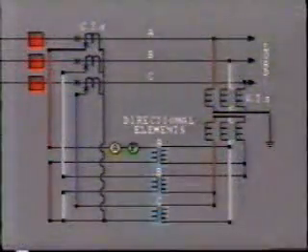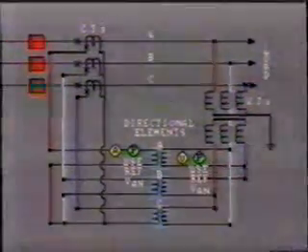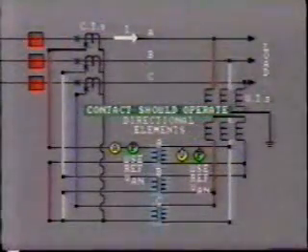To check the phase relay, the load current magnitude, direction, and power factor must be measured accurately. Also, the value of current and its phase angle provided to the phase A directional relay. The phase angle meter should use as a reference voltage the A phase to neutral, VAN. If a phase angle meter is not available, a watt meter could be used with its voltage coil connected phase A to neutral. We must also accurately measure the voltage input to the relay and its phase angle relative to VAN. This will enable us to draw a phasor diagram indicating the relative phase displacements of current, IA, and the polarizing voltage. With current flowing in the designated tripping direction, usually into the line, the directional element contact should operate.